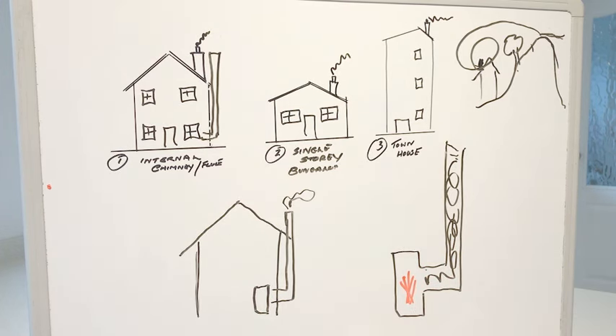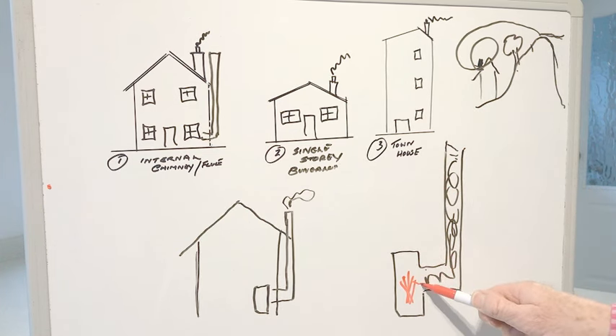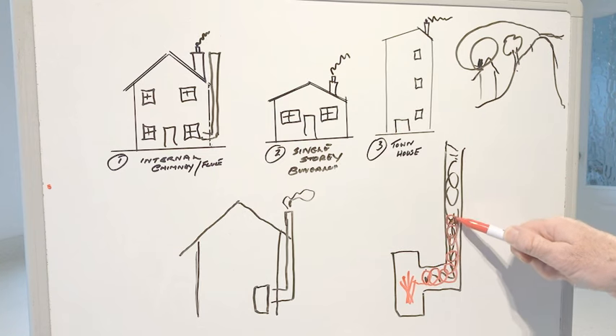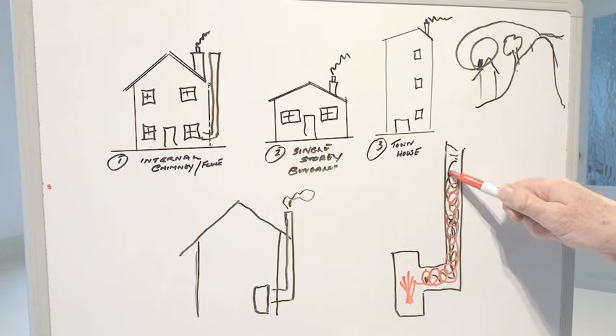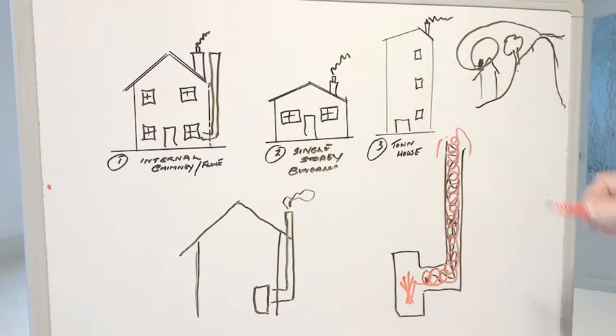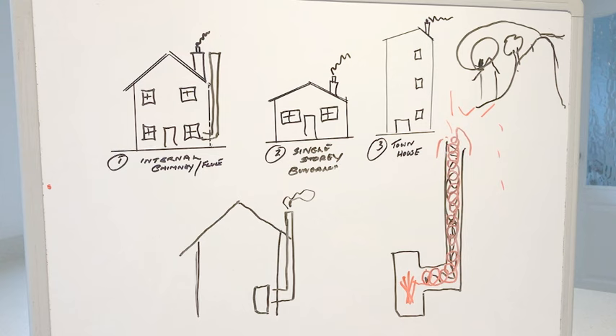It's no good lighting a conventional fire with wood straight away, because that's going to create smoke and you'll have the problem immediately. What you've got to do is put a source of heat at the base of the flue — it will slowly work its way up in a vortex, round and round, battling the cold air and pushing it up and out. Once you've successfully corkscrewed all the way up that flue, the cold air will come straight out the top and the hot air will take over. The key is creating that heat source without smoke.